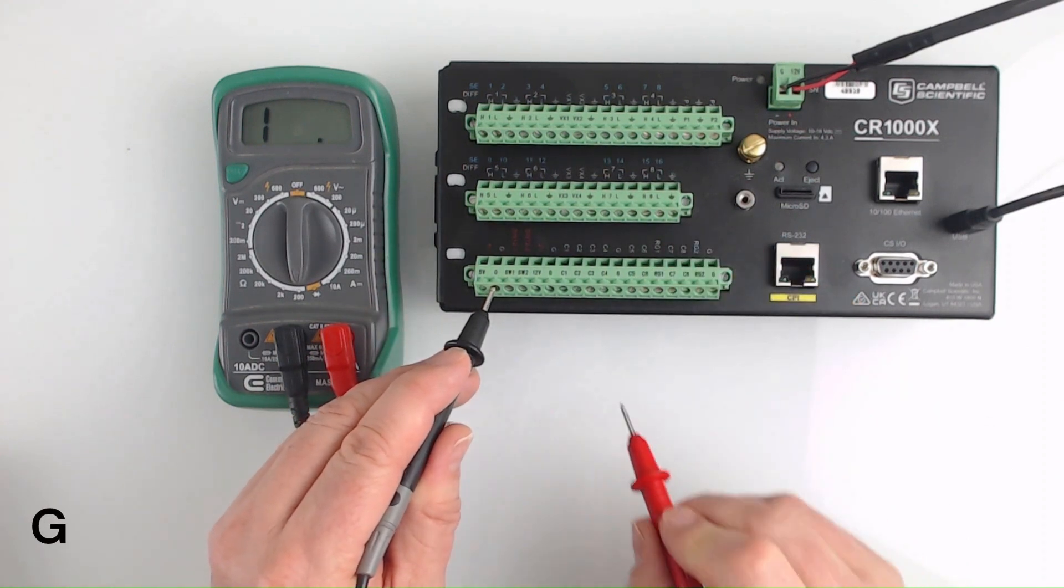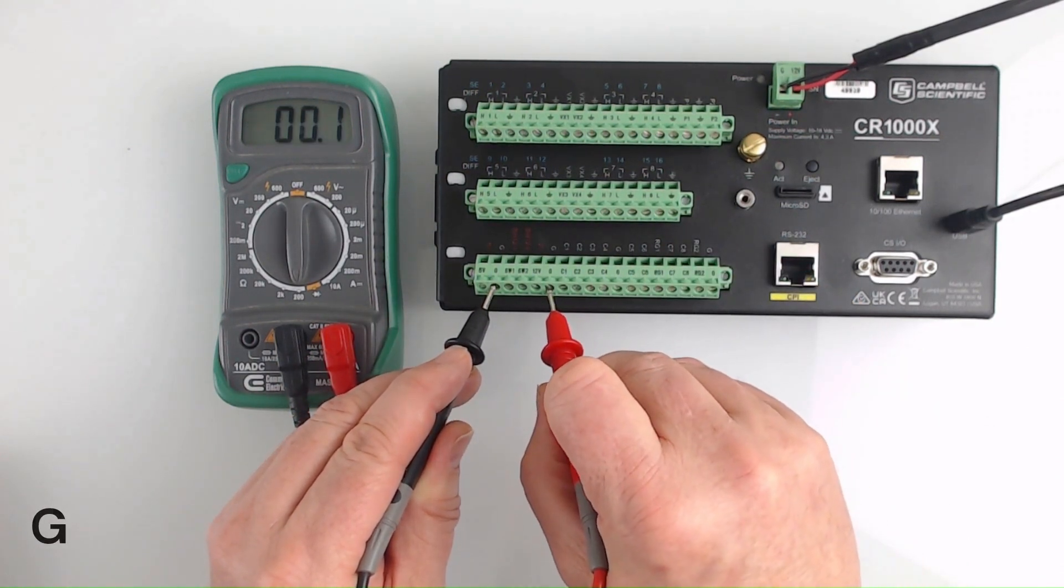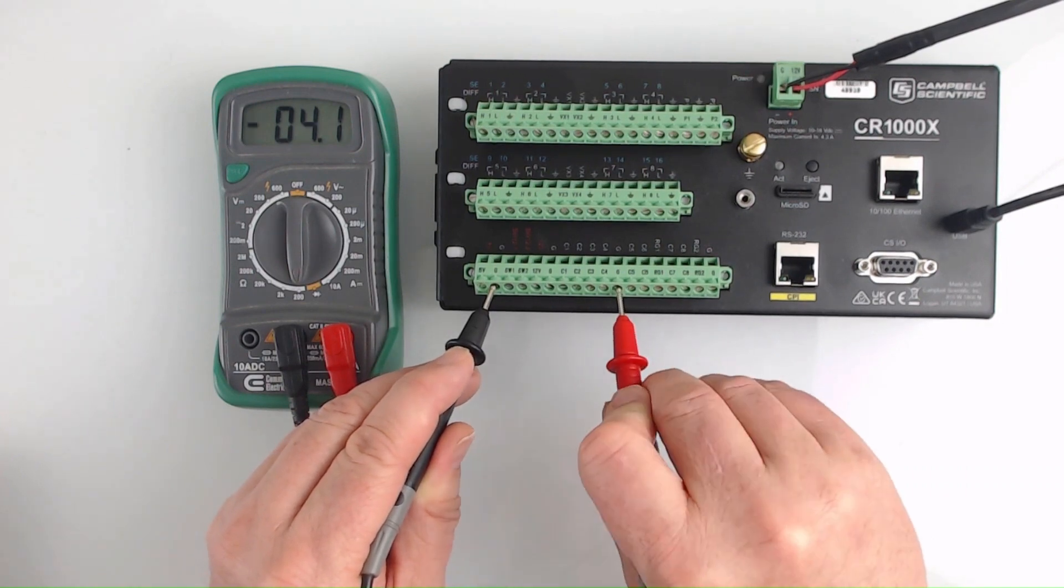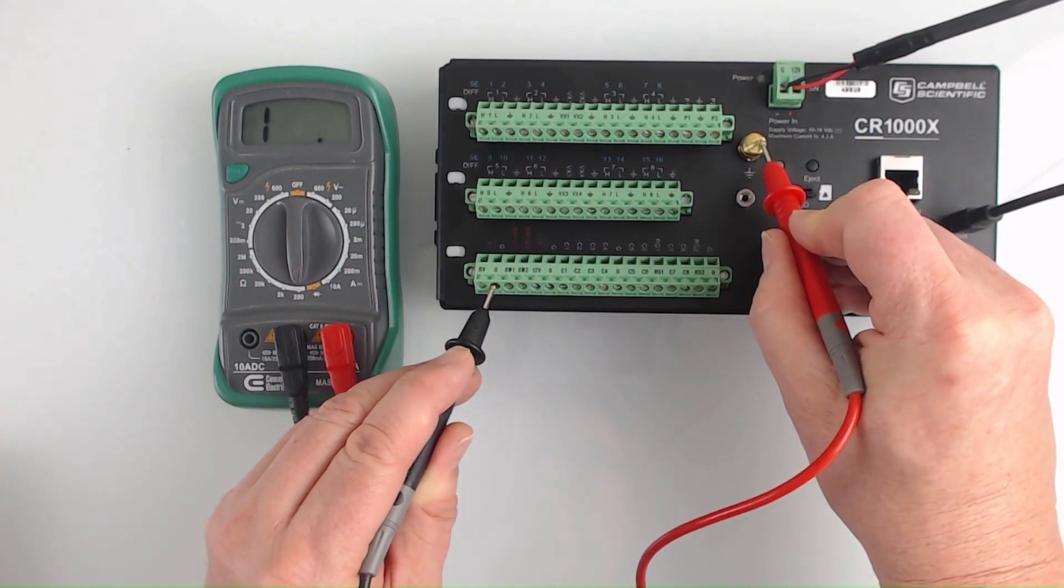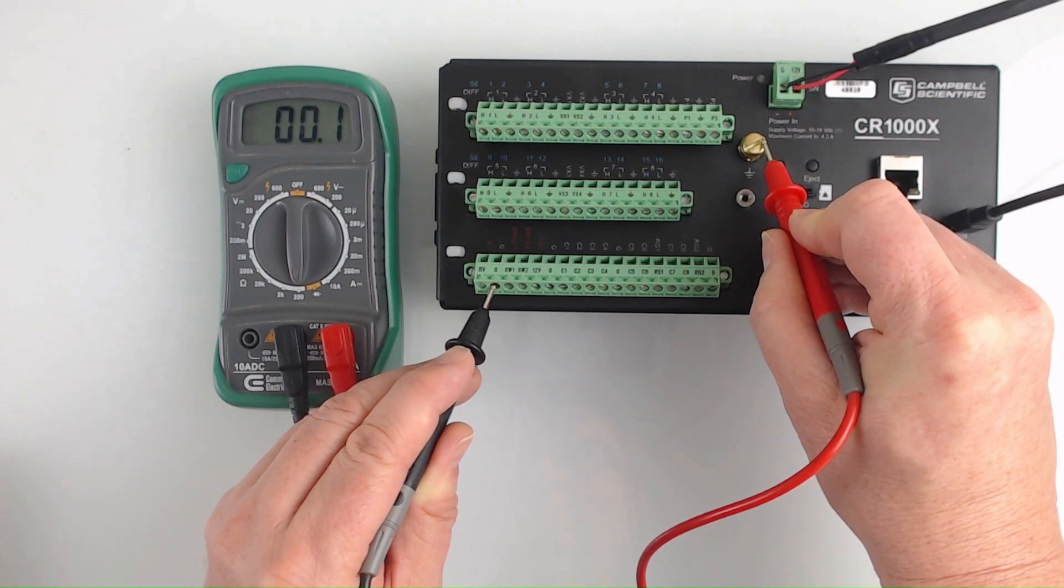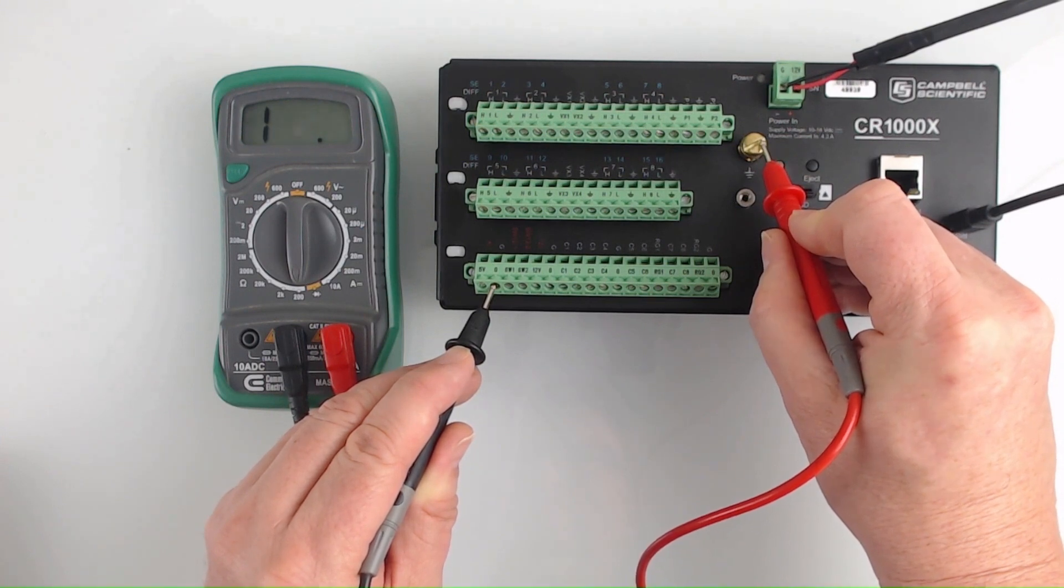Similarly the channels labeled G are called power ground and are all connected to each other and to the ground lug. If you detect a break in continuity between the signal ground or power ground channel and the ground lug contact Campbell Scientific to arrange for repair of your datalogger.